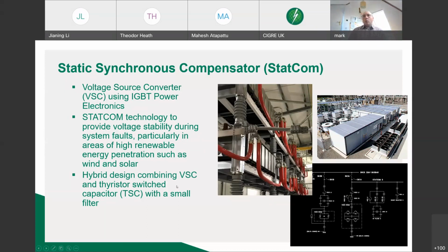Now that is fine providing you want a symmetrical injection, and in a lot of cases that is what people want. But in the case of economics, these systems are still more expensive than the traditional SVC elements. So quite often you tend to see requests for a hybrid design, and that's what we have on our network. Essentially you're looking for something in the order of 100 or so MVARs inductive, but primarily we're also looking for voltage support when you get that big voltage dip after a fault. In our case, a lot of ours are specified for in the order of about 200 to 225 megavars capacitive injection. So that's very, very expensive as a singular STATCOM solution.